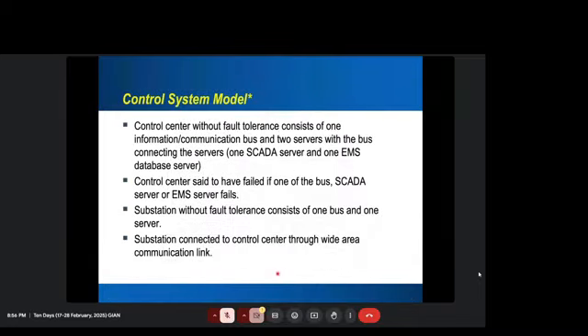So in terms of control system model, we do want fault tolerance, and without fault tolerance it will be a problem. We can have multiple ways of building the control center. If there is no fault tolerance, it will have only one information communication bus, if you don't have redundancy. With 2 servers on the bus-connected server, one SCADA server and one EMS database server, there's no fault tolerance in this, because if this fails, then there's no backup.